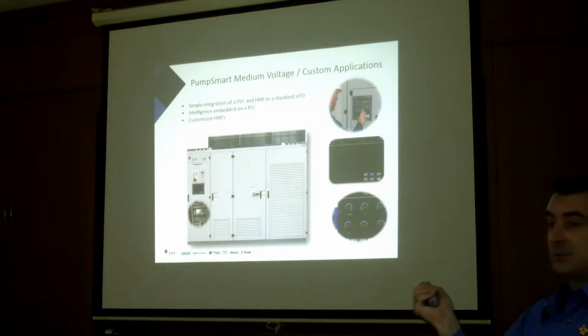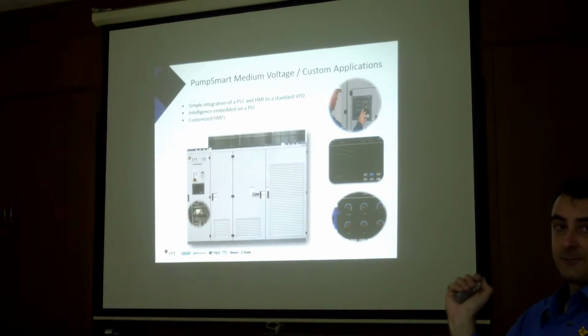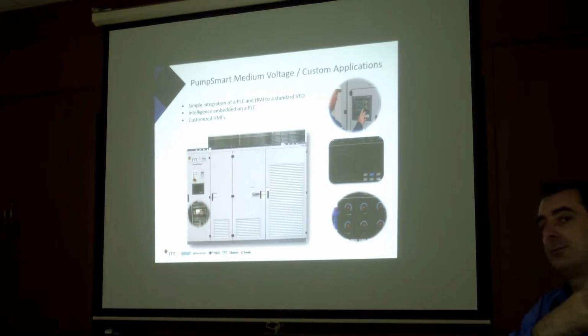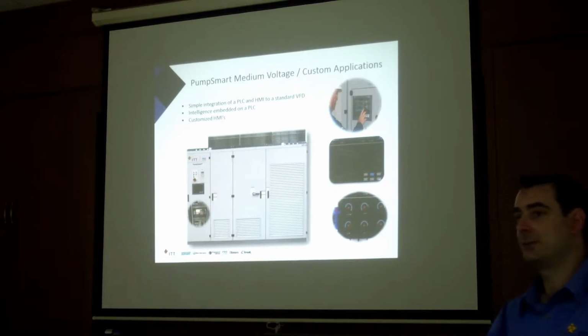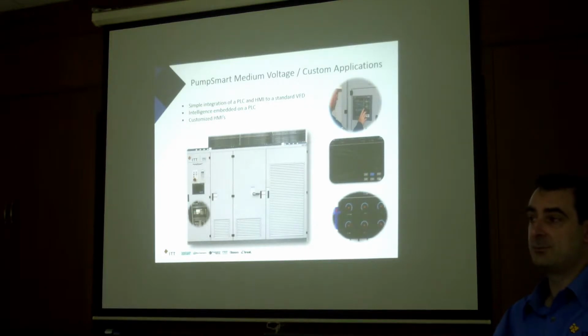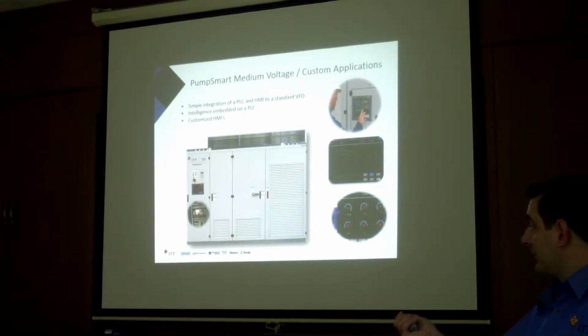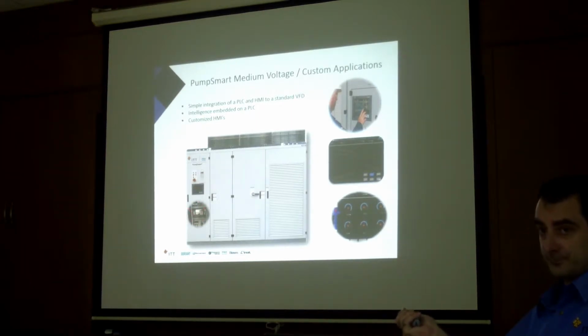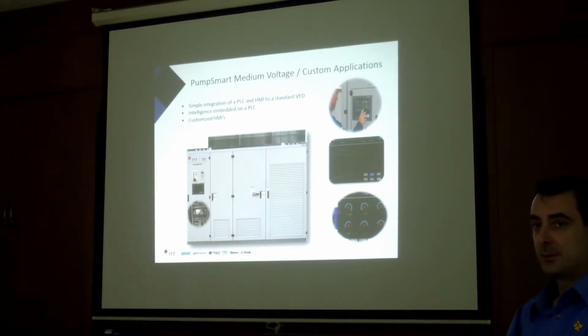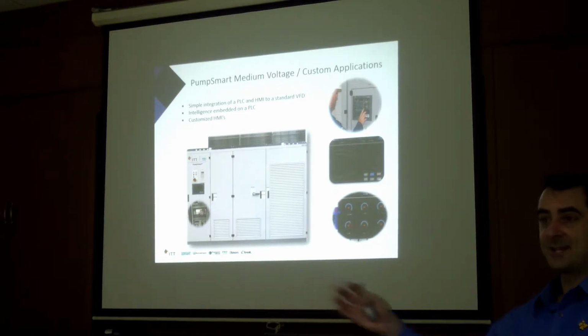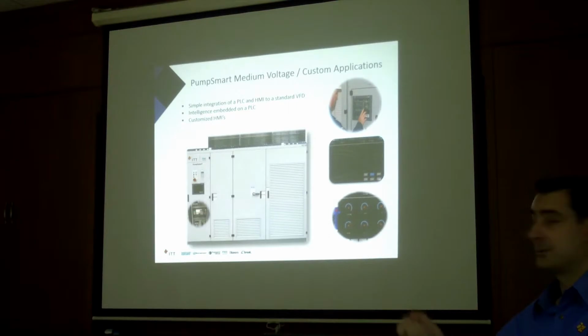But medium voltage, we are okay with almost any brand, and we do. Actually, less than 50% of our medium voltage drives are ABB. We work closely with ABB, and if the customer has no preference, we will use ABB most likely. But if you look in ePrism, you'll see pricing for Toshiba and Rockwell. If you want Siemens or Schneider, it doesn't matter, we can do it, because all the Pump Smart logic sits in a separate PLC and integrates into the cabinet. We do need to specify the variable speed drive. So the customer will have a specification, ITT has a specification, and together we can get a Pump Smart.